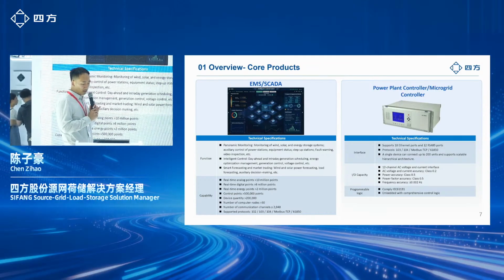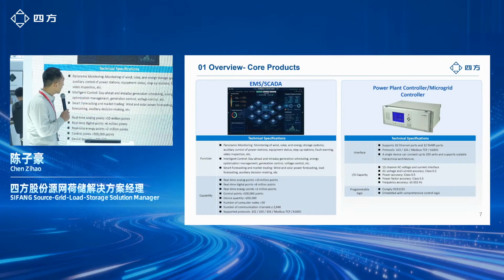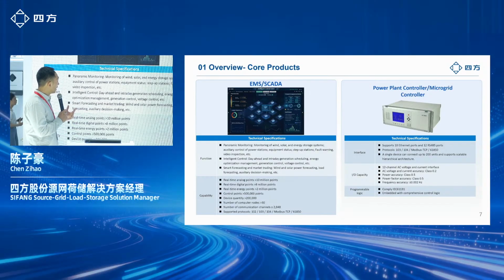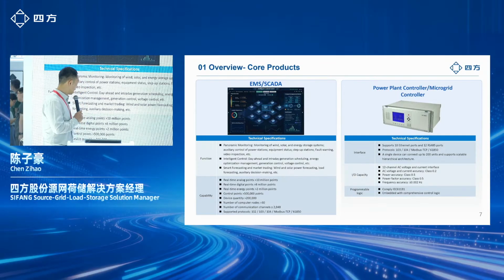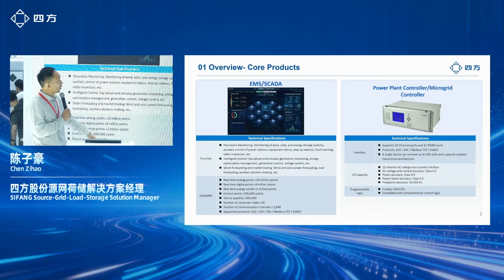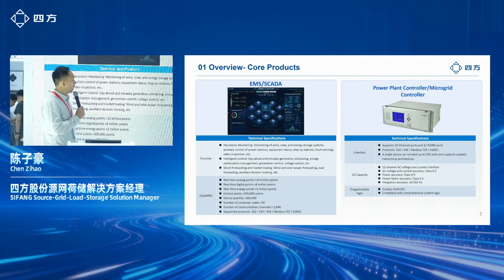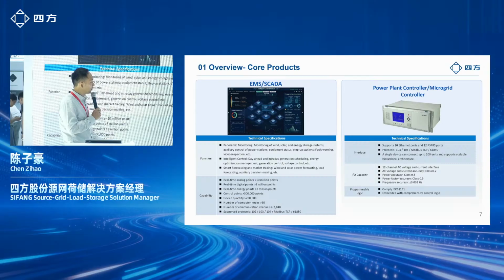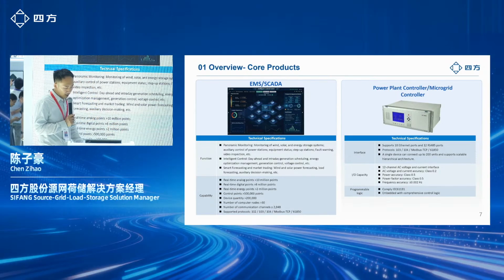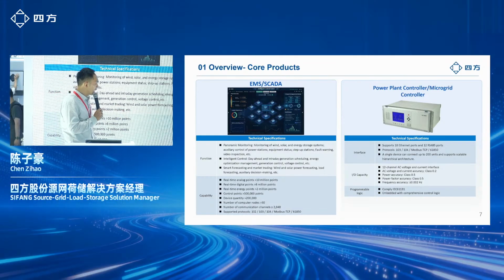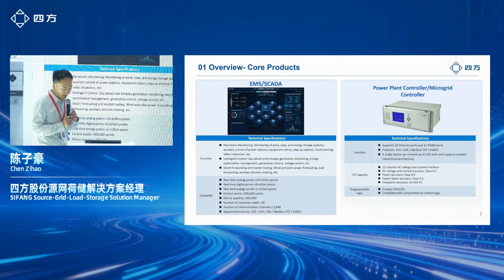And also we support the whole dispatching process based on the mainstream protocol like the 104, 61850, and the Modbus. Another key point is our controller. The interface is multiple and is flexible to different protocols. And our programmable logic complies with the IEC 61131. And one single device supports more than 200 subunits.